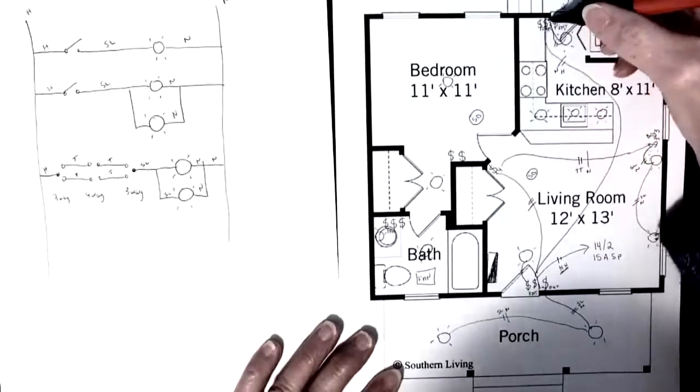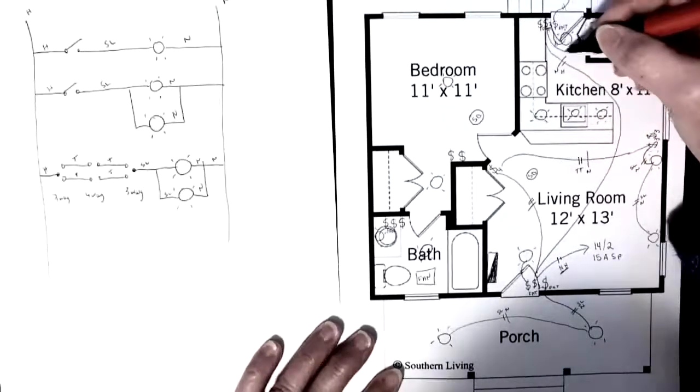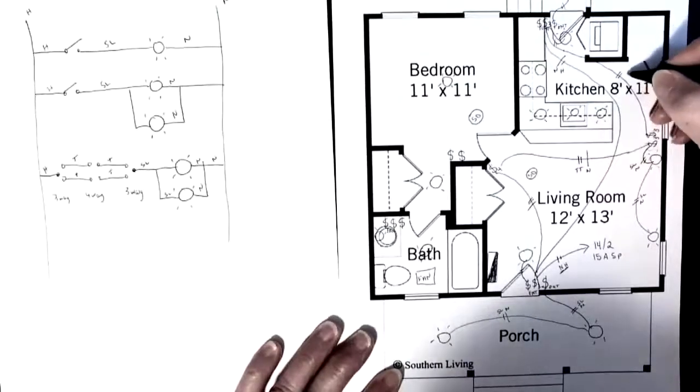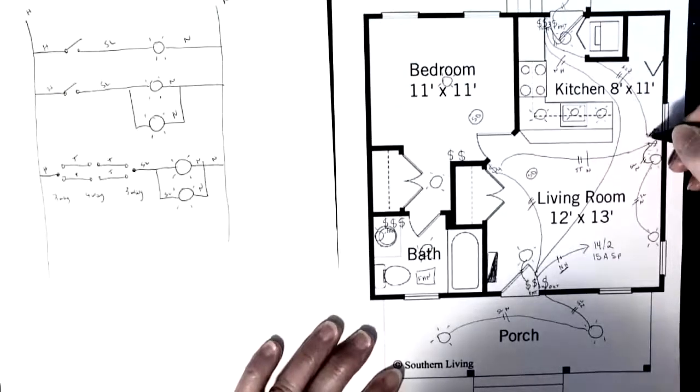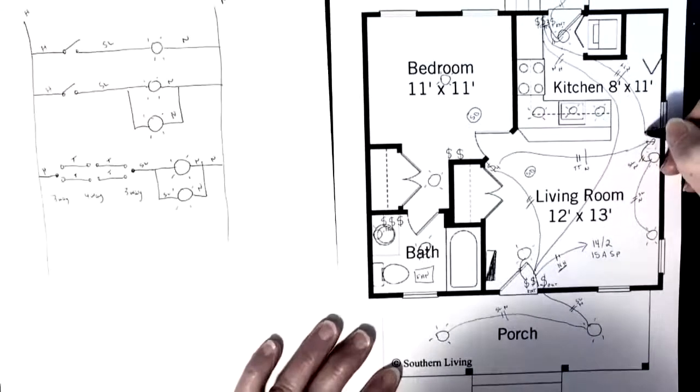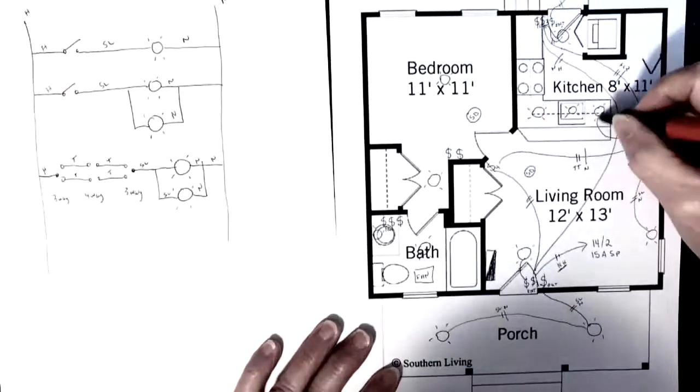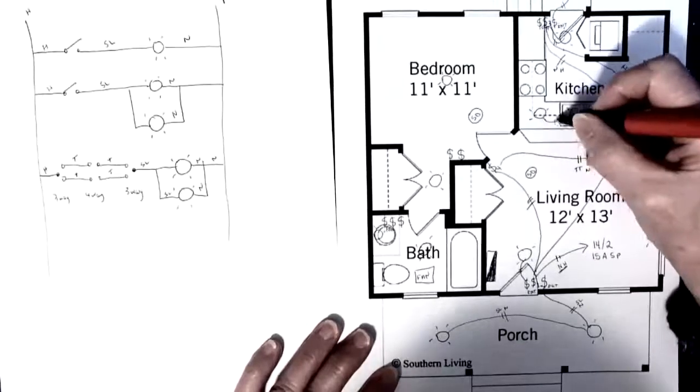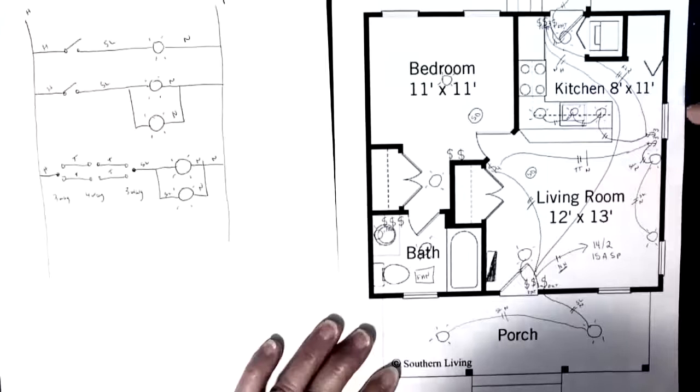So right now, I have a hot and a neutral at this end. What I need to do is take a three-wire over to there, so that my traveler, traveler, neutral are now going through. And then from there, I can take a two-wire off to my three pot lights, and just join them in parallel. So I'll show you what this circuit looks like now on the schematic.